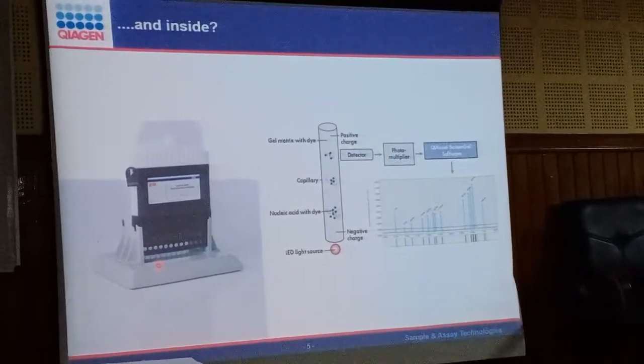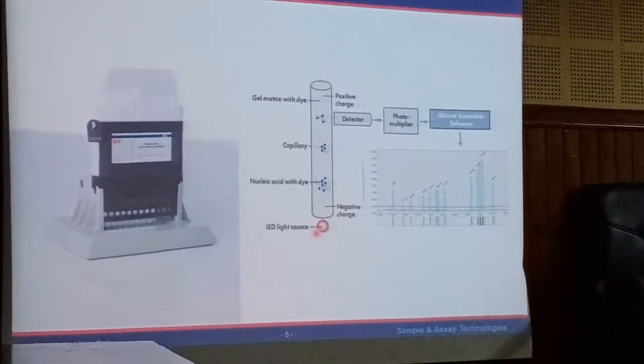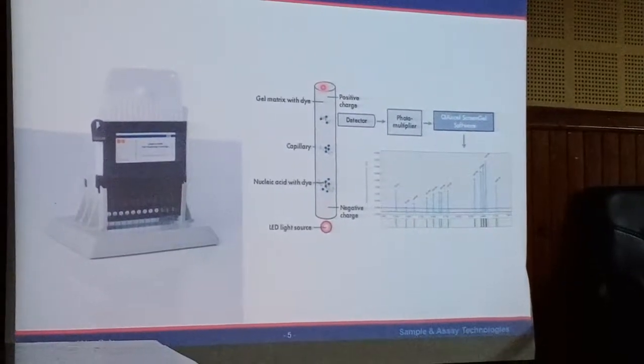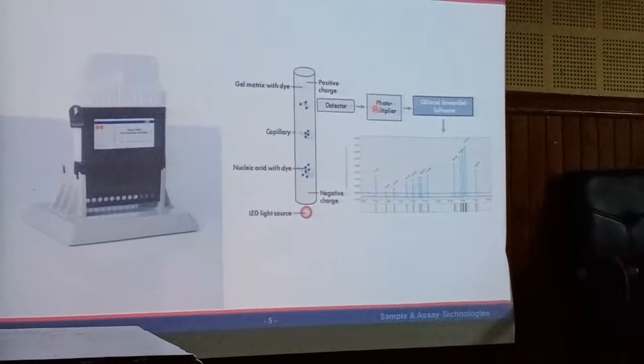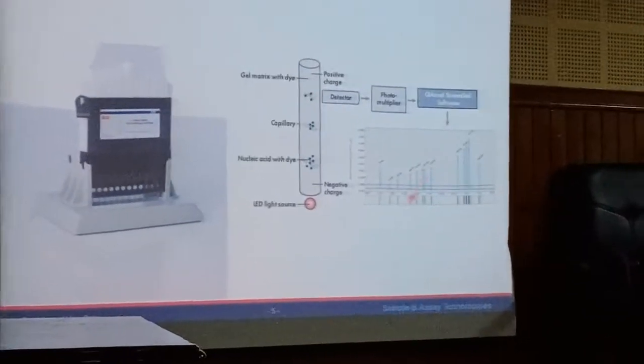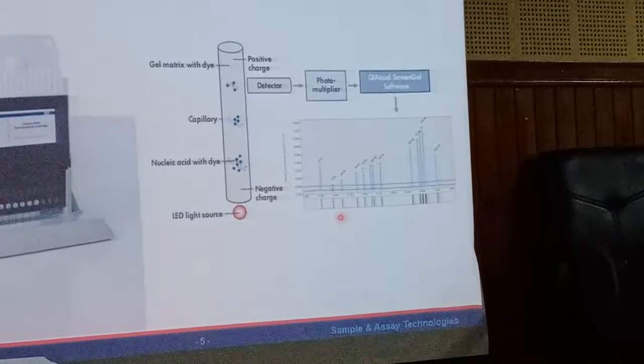This is the cartridge — it's actually a 12-capillary cartridge. The grey colour is the stand, and we have individual capillaries. There is an LED light source at the bottom which illuminates the sample. The sample runs towards the positive electrode, and when it crosses the detector, the signals are amplified in a photomultiplier tube. The ScreenGel software converts the analog signals to digital, showing you a gel dock image as well as an electropherogram — the vertical image has been displayed horizontally to align with the electropherogram.